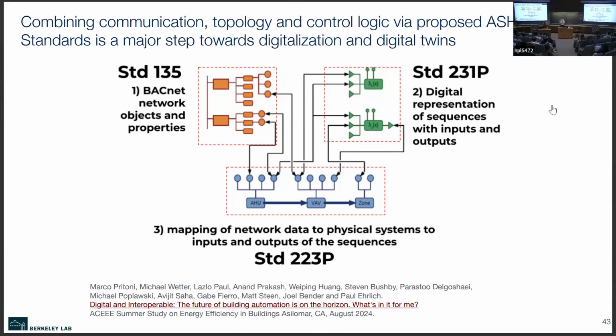BACnet basically deals with the communication of control signals. Standard 223, for semantic interoperability, specifies a topology—for example, which air handler unit serves which zone. This topology can then be used to semi-automatically configure the control logic that's exported according to Standard 231.